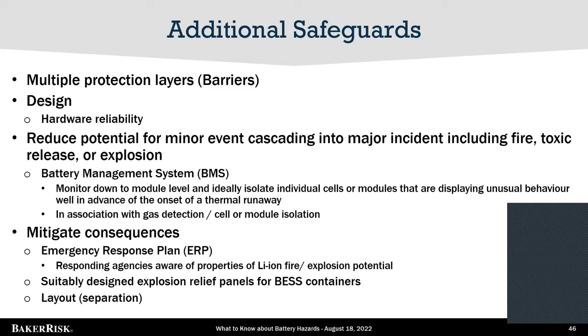If something has already happened, you need an emergency response plan. Responding agencies need to understand the potentials—how bad it could be and the best way to fight that fire. We can also talk about explosion relief panels, and an important factor we've seen specifically in the Australia event shown earlier is the layout or separation distance.